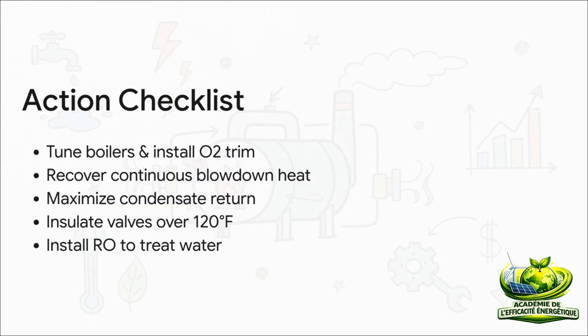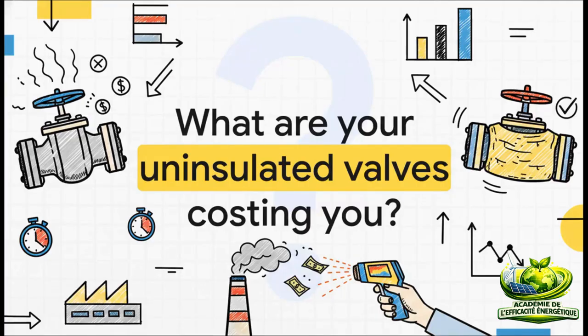3, maximize every drop of that hot condensate return. 4, insulate every single valve and flange that's running over 120 degrees. And 5, this is a really great pro tip from our sources, install a reverse osmosis or RO unit to pre-treat your incoming water. If you filter out those minerals from the start, you won't have to blow down nearly as often. So, I want to leave you with this final thought today.